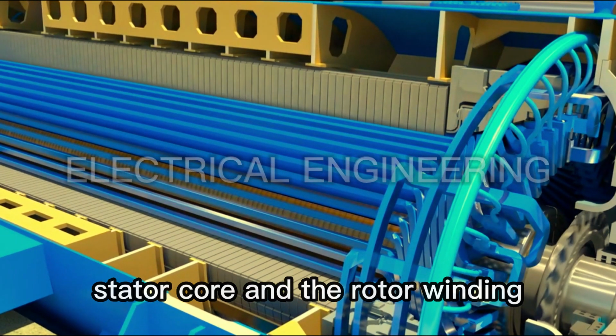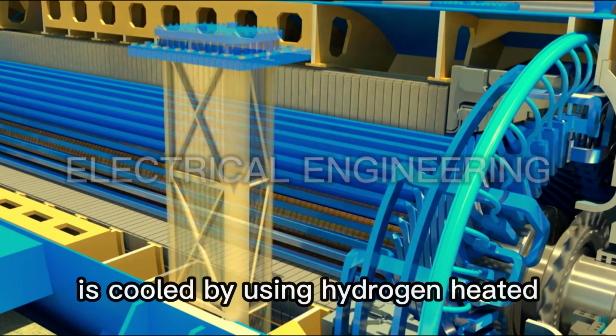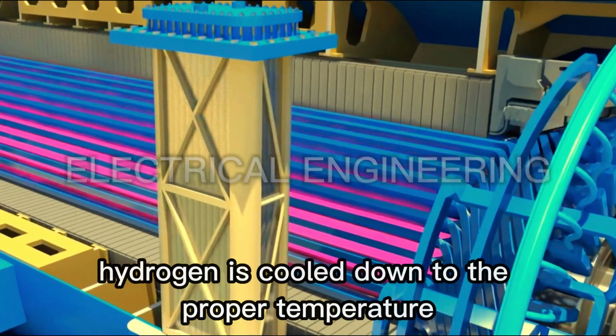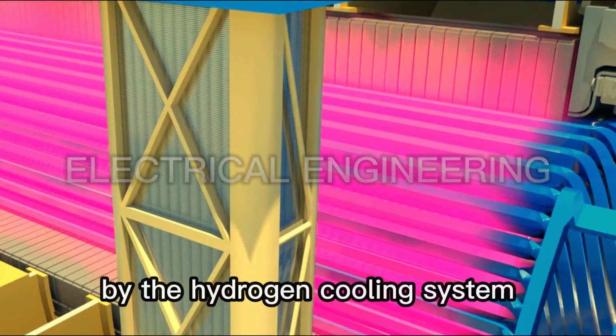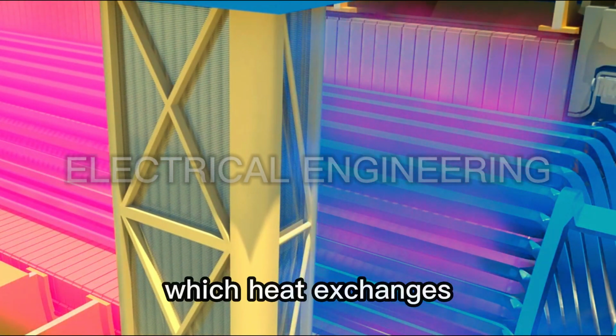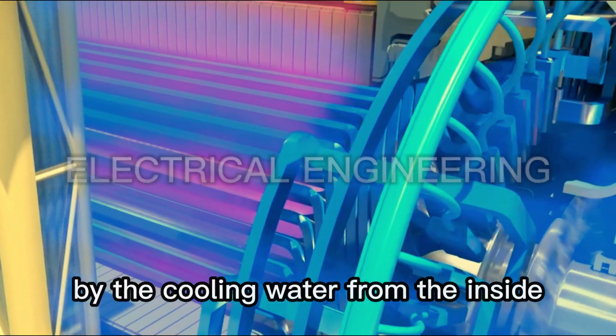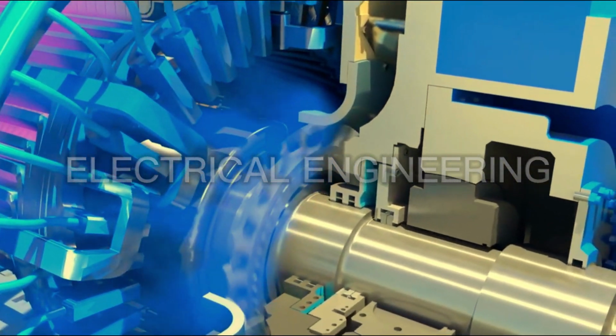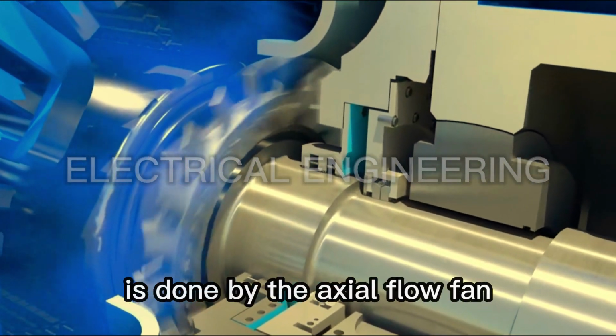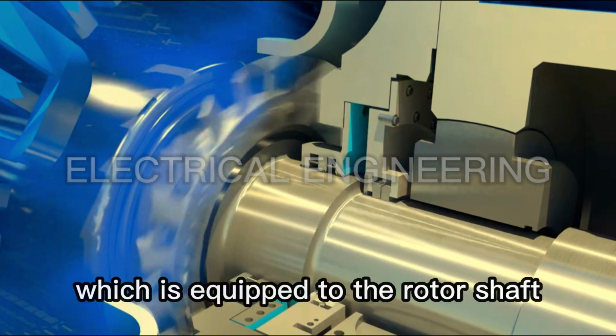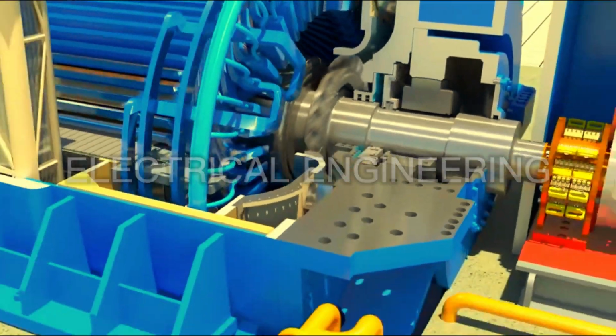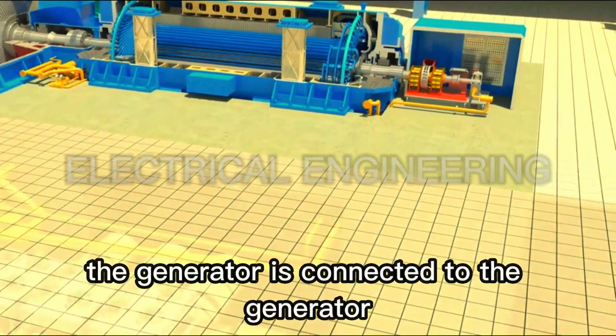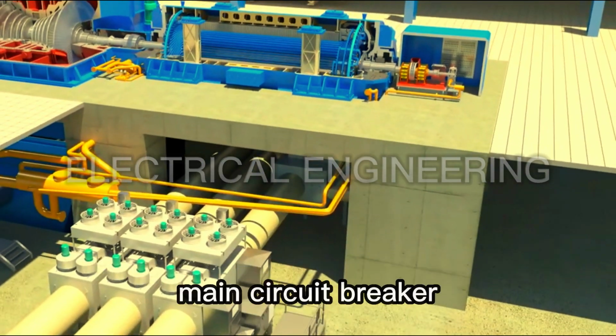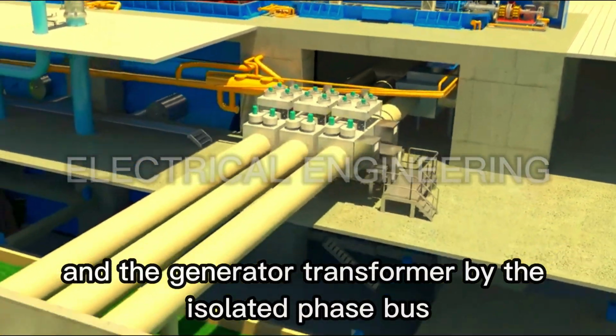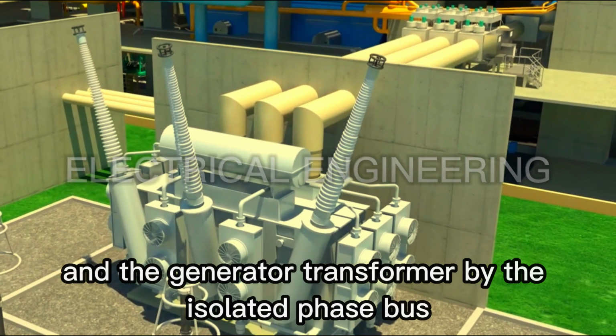Stator core and the rotor winding are cooled by using hydrogen cooling. Hydrogen is cooled down to the proper temperature by the hydrogen cooling system, which heat exchanges by the cooling water from the inside going through the hydrogen cooler. The ventilation of the hydrogen is done by the axial flow fan, which is equipped to the rotor shaft. The generator is connected to the main circuit breaker and the generator transformer by the isolated phase bus.